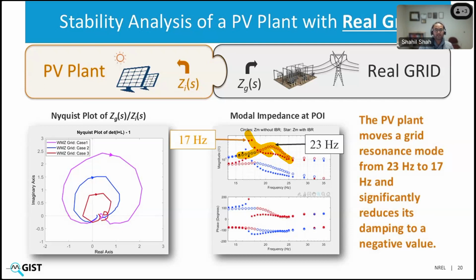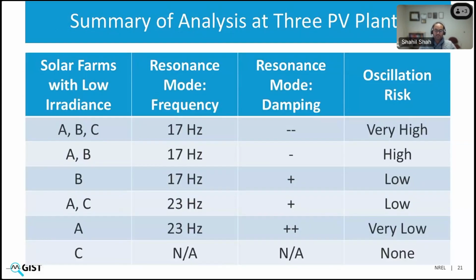So it really shows you how the PV plant is impacting the damping of an already existing mode within the grid. Now we repeat this analysis at different IBRs, and as Nilesh was saying, 3 or 4 IBRs were found to be the key source for this oscillation. So I'm just showing you the summary of analysis of 3 PV plants. On the left column is basically PV plants with low irradiance. Here is the resonance frequency and damping within the system for that particular condition, and then the oscillation risk. Let me start with the bottom row. So plant C, if there is only one plant in that region, plant C with low irradiance, there is no resonance mode in the system based on the impedance analysis, and the oscillation risk is none.